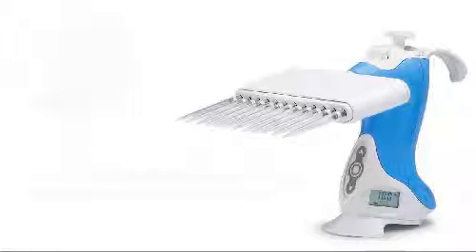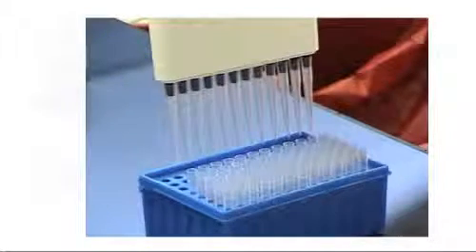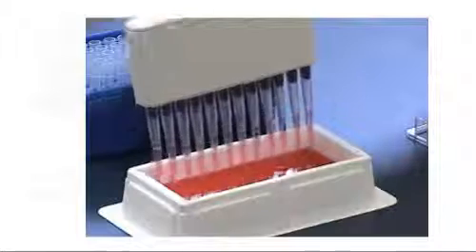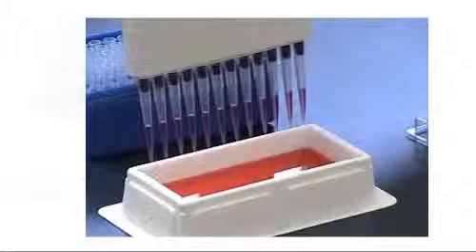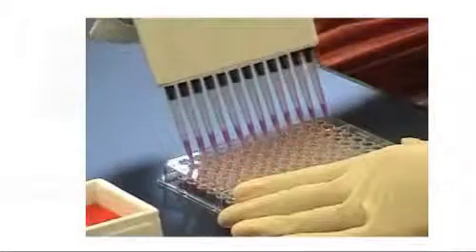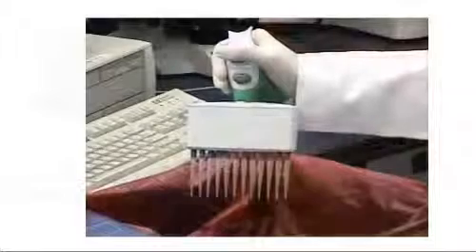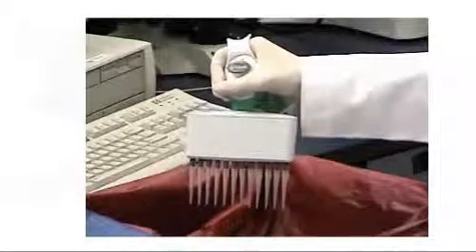Take a look at the Ovation multichannel in action. Ovation's low profile makes it easy to visually align its nozzles with tips. The user simply presses down until Ovation clicks, indicating all tips have been securely acquired. Pressing the pipetting trigger aspirates the sample. Pressing the trigger again dispenses the sample. By holding the trigger, a multiple sequential dispensing feature called Pace is activated. Pressing the Tip Eject button discards all the tips quickly without effort.